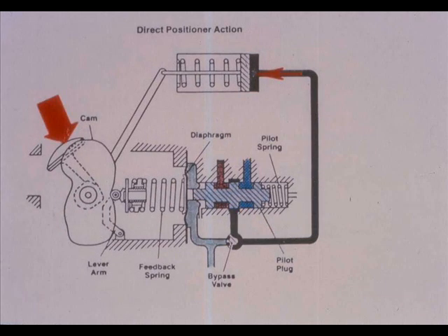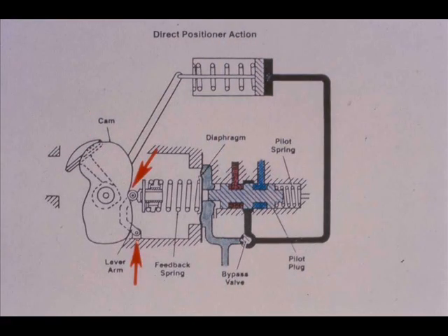The increasing pressure to the actuator moves the valve plug. The actuator and valve plug movement causes the cam to rotate. The lever arm is pivoted at one end, and the cam follower end rides on the cam as it rotates. The cam transmits the valve plug movement through the cam follower to the feedback spring, compressing the spring.